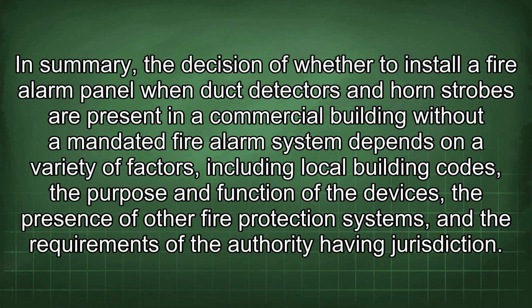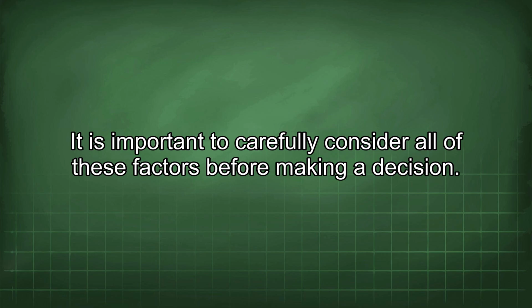In summary, the decision of whether to install a fire alarm panel when duct detectors and horn strobes are present in a commercial building without a mandated fire alarm system depends on a variety of factors, including local building codes, the purpose and function of the devices, the presence of other fire protection systems, and the requirements of the authority having jurisdiction. It is important to carefully consider all of these factors before making a decision.